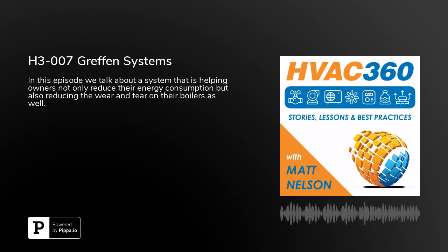Okay, well, our principal product is a microprocessor-based device that works with closed-loop hot water boilers. Typically, hot water boilers, which are very efficient and operate very well compared to alternatives, still have some areas where they can be improved on for efficiency, and we work with that, principally with boiler cycling. So what our product does is we match demand to boiler operation. Typically, we can cut 30 to 50% of the duty cycles out of an operating forced draft boiler, and with that we get energy savings anywhere from 10% up into the 20% range.